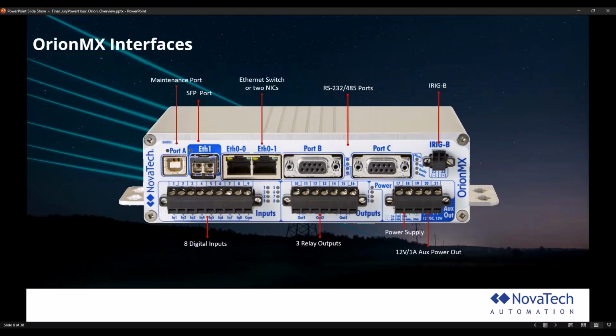All right, let's talk about it. This is indeed a Swiss Army knife as far as RTU type appliances go. This is kind of the littlest member of the family here, but it carries with it on every one 8 DI, 3 DO, and one of the DO is actually Form C, so you've got an A and a B contact on output 3. You carry a wide range power supply. There's also a low voltage option, so you're talking 12 to 24 volts. But when we're talking about wide range, we're talking 24 volts to above 240 volts, AC or DC. So it's very, very versatile. Like you don't have to worry about it. It's good for standardizing on things where it just works across the whole range of applications you might need.